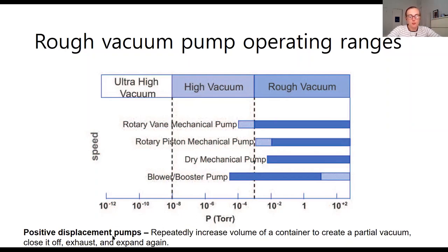Most of the rough vacuum pumps are all positive displacement pumps where you will be changing, collecting some of the gas in the system, then closing that off from your chamber and then displacing that gas so it exits and then repeating the process over and over again.